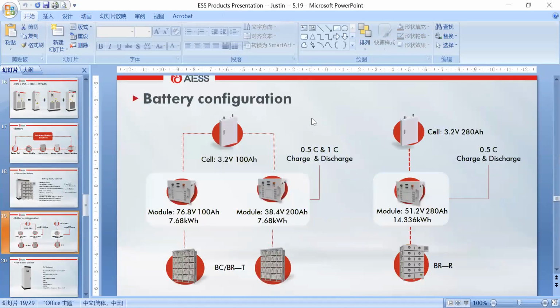Let's see over the battery configurations. We have two types of battery cell. I've set up plans from our left side. For this battery cell, it's 3.2 voltage with 100 amperage. We can make two different modules. The first module is 76.8 voltage with 100 amperage, and the second one is 38.4 voltage with 200 amperage. But both of them, the battery energy is 7.68 kilowatt hours.